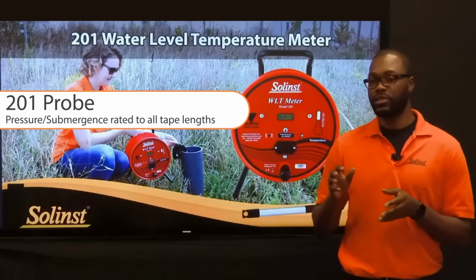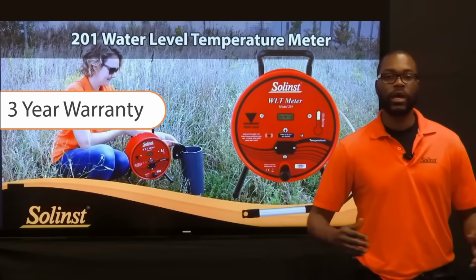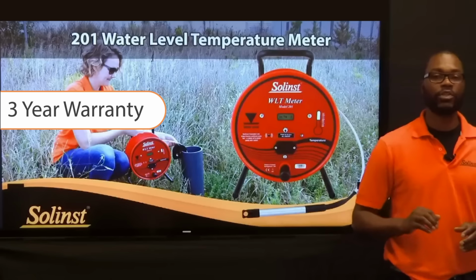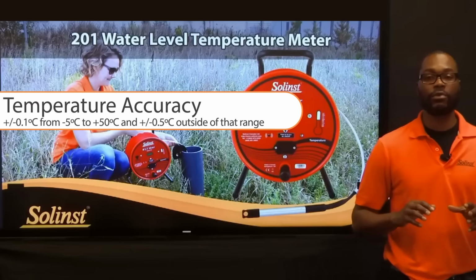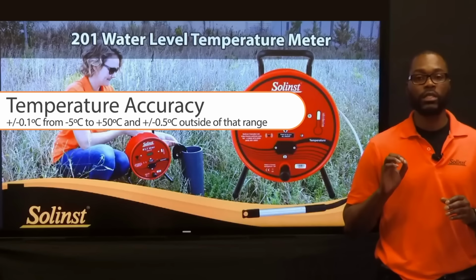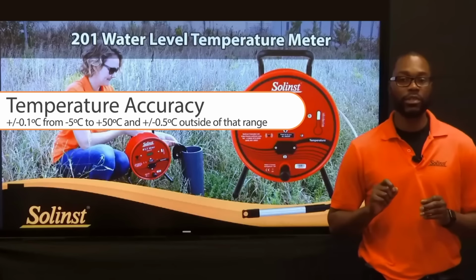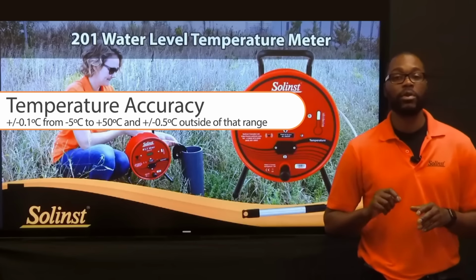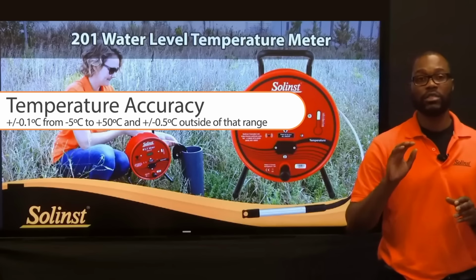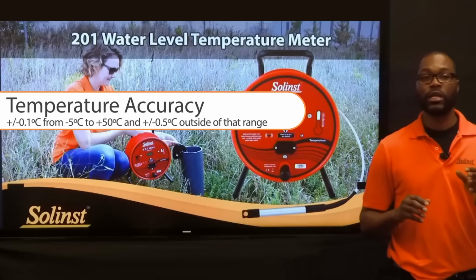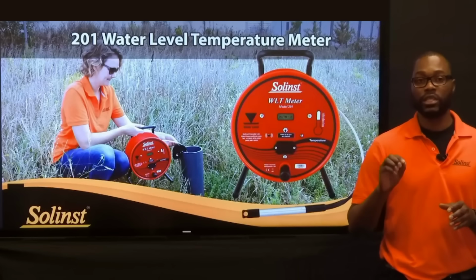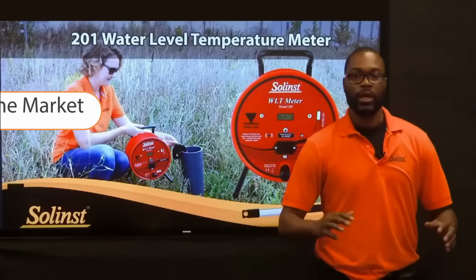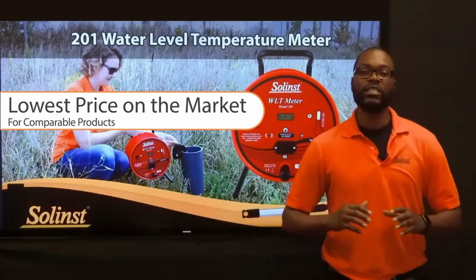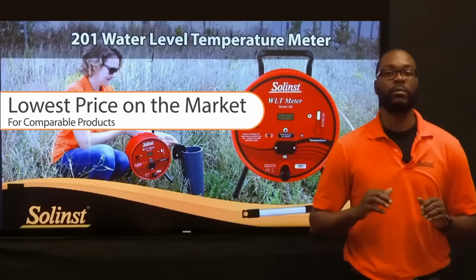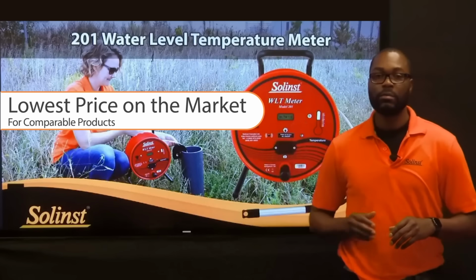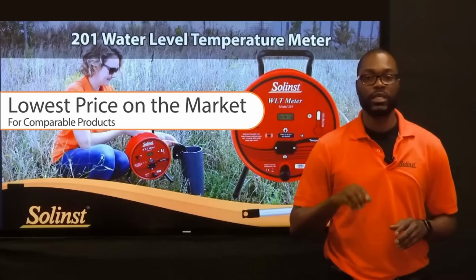Solinst also backed this equipment up with its 3-year warranty. But it doesn't stop there. The Model 201 water level temperature meter has a temperature recording accuracy of plus or minus 0.1 degrees Celsius from -5 degrees Celsius to 50 degrees Celsius, and plus or minus 0.5 degrees Celsius outside that range. This meter sports our laser mark PVDF flat tape, which is very durable and chemical resistant, and a very competitive price. You have an easy decision to make when sourcing a water level temperature meter for your next application. The Model 201 water level temperature meter is simply the best.